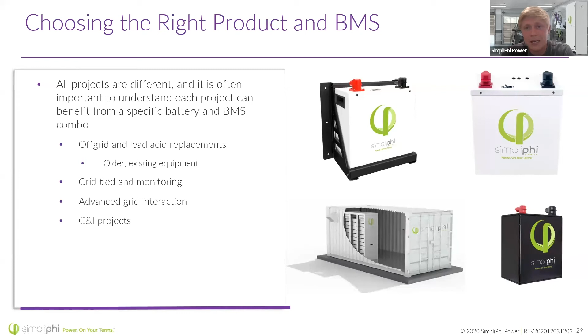And another thing to consider is weather, right? Our PHI battery does not have cold temperature protection built in. So if you're planning to install in a freezing environment where you're not heating the batteries and you're not taking them inside in the winter, then the SimpliPhi BMS is the one for you. Now, it can be used without communications, and it still has that cold temperature protection built in. I think that it works far better with communications, however, as the temperature protection is first going to ramp down the charge current from the inverter, and then finally does have that disconnect built in. And again, one other consideration is commercial and industrial, right? Often the amount of power and the type of power you need, maybe you need 480 volts and 500 kilowatts of power, that's going to be looking at a high voltage product. Can almost guarantee you.